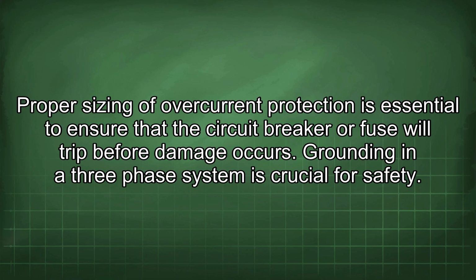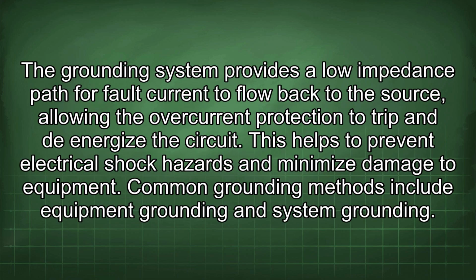Grounding in a three-phase system is crucial for safety. The grounding system provides a low impedance path for fault current to flow back to the source, allowing the overcurrent protection to trip and de-energize the circuit. This helps to prevent electrical shock hazards and minimize damage to equipment.